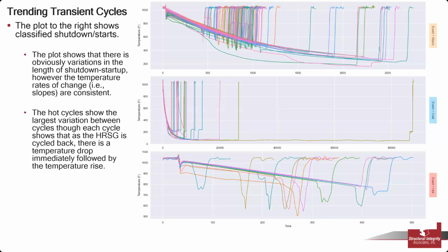So there's always a little bit of a caveat there of, you don't know exactly the operation prior to the installation of additional, local thermocouples, but generally, you're going to have to make assumptions and see where you land, and that's where ultimately all monitoring that we're doing is accompanied by inspections to baseline and validate the accuracy of the model.